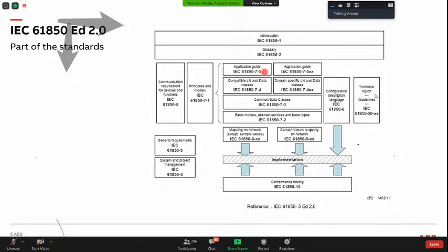Yeah. So the application guide explains substation automation functionality. Then there are data models. There are many things required in the standard, and there is one final part called 10, which is a conformance test. If some manufacturer like ABB says that my device is as per the standard, someone should make sure they have actually implemented it as per the standard. So there are specific parts which tell how this has to be tested to make sure that somebody has implemented this standard in their devices.